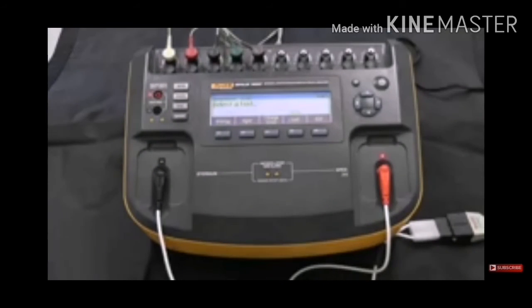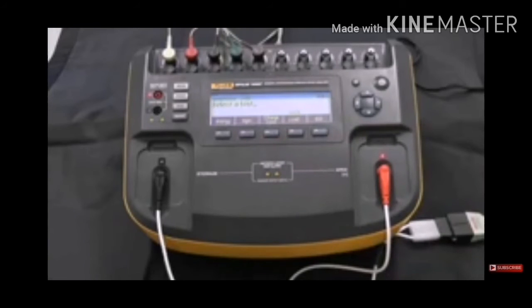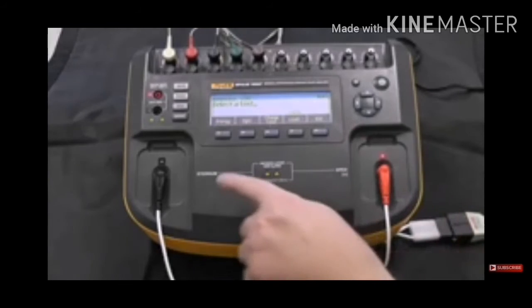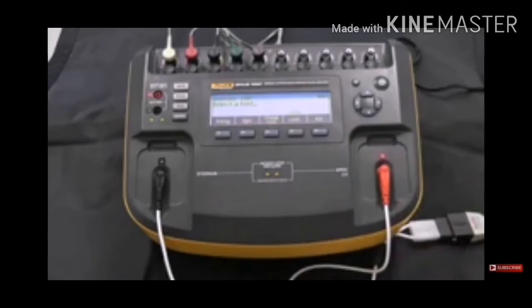And so let's start with defib. Now you can see here that once we have selected defib as the category that we want to test, now we have different kinds of tests that we can do. Energy, synchronization time, charge time tests, and we can select a load. If we have the 7010 external load accessory, we could select our load there. Otherwise, as you see here, we're selecting the internal 50 ohm load. All right, so let's pick the defib energy.